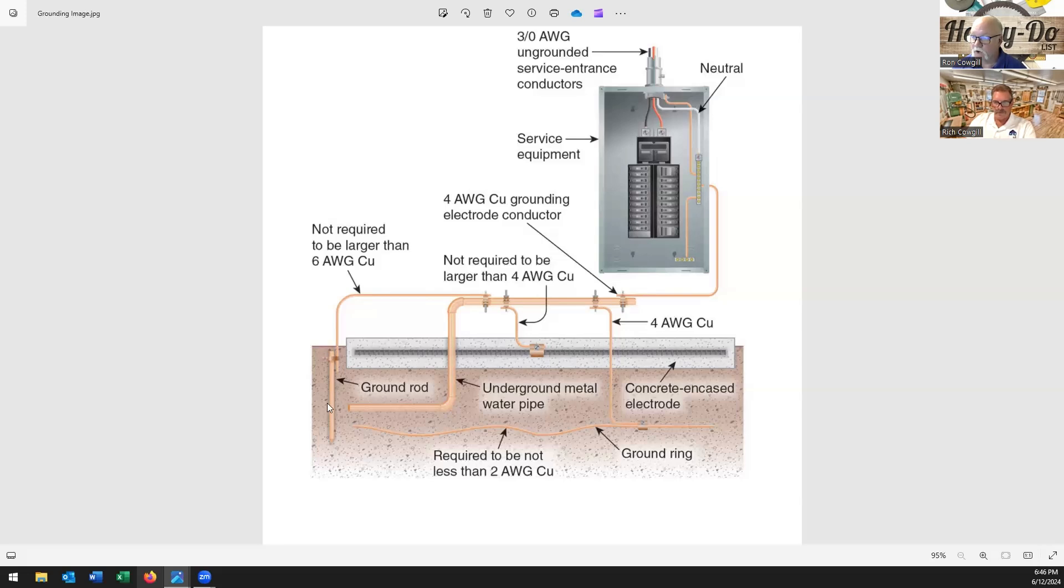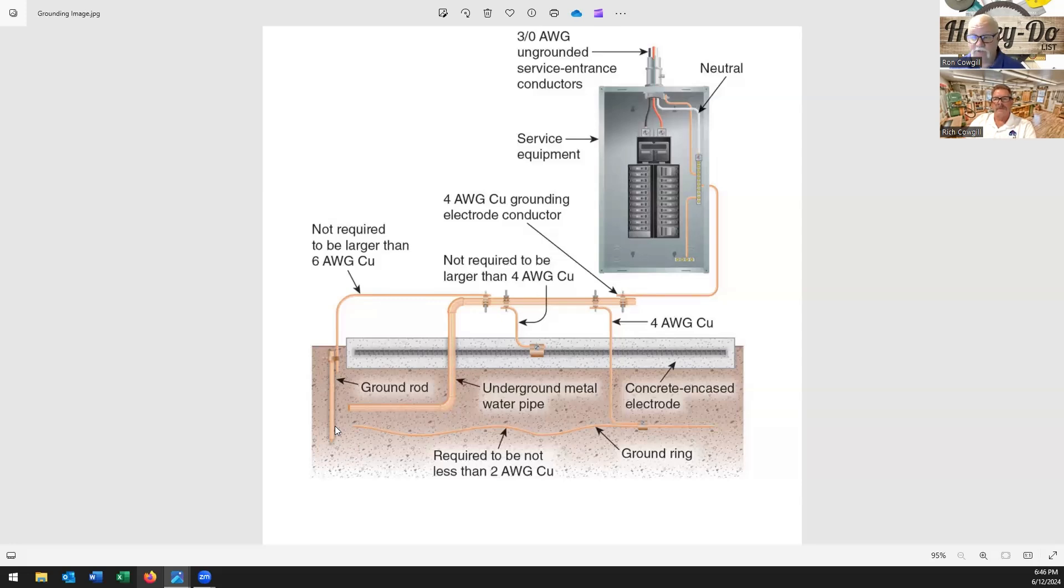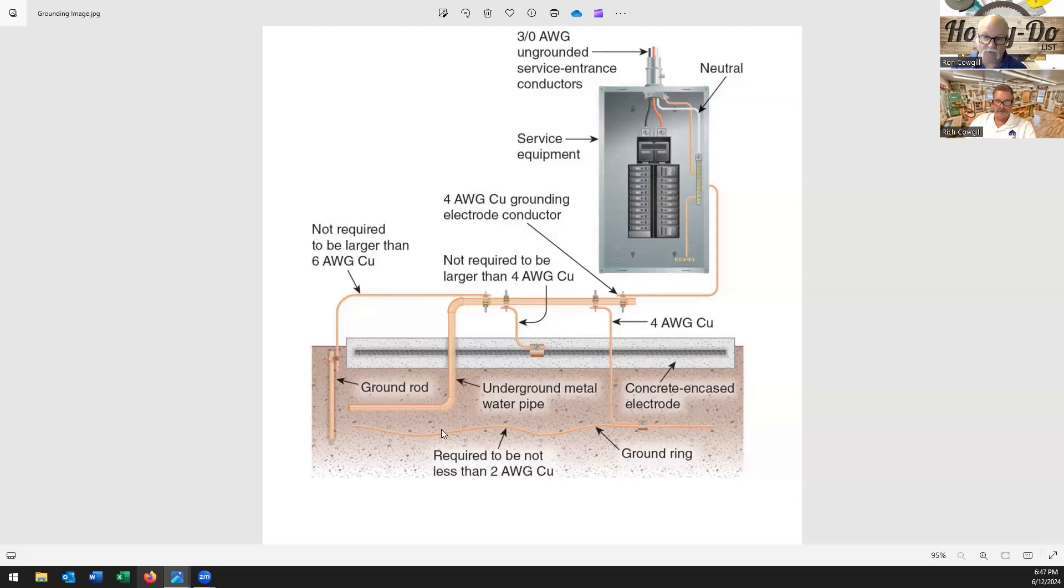On these ground rods there's a minimum of two that's required because there's no way to really test the impedance of these, so that's why they're requiring two, minimum of six feet apart and eight feet long. Obviously different parts of the country you can't get an eight foot ground rod in, so that's why you've got these different types of wires, plates - there's all different sizes. And if you go to the NEC that'll show you exactly all your different options for getting proper grounding.